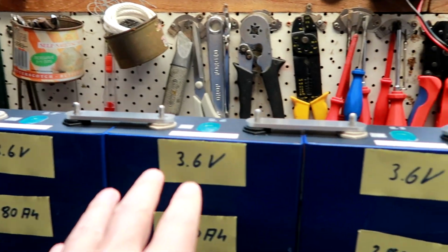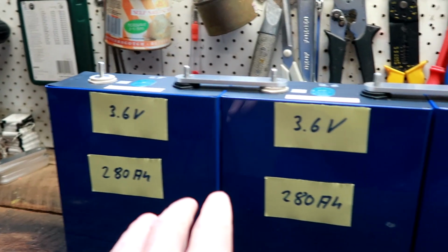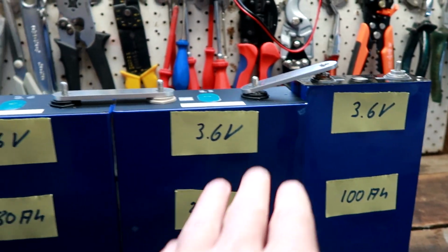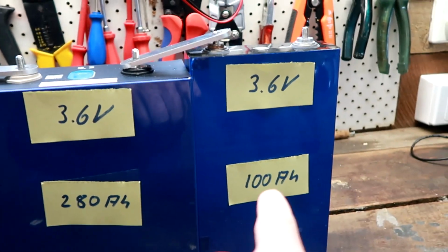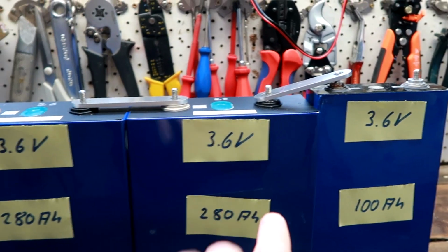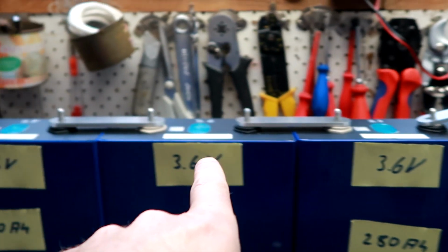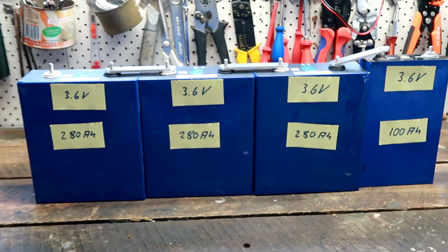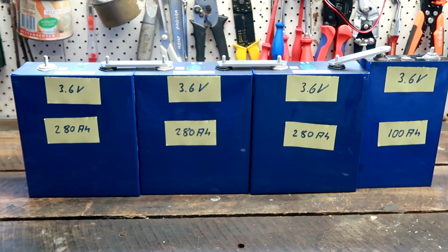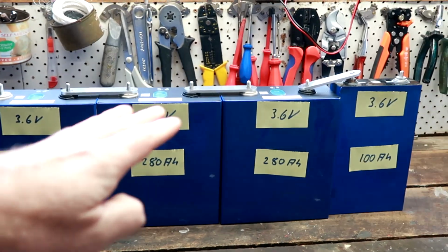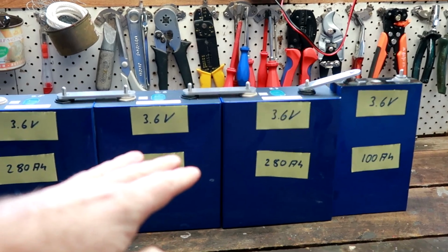3.6 volt, 3.6 volt, 3.6 volt, 3.6 volt. After balancing, you know, you did the balancing with your power supply. Everything is 3.6 volts and you've got them charged to the maximum state of charge at 3.6 volts per cell. They have, however, different capacities. But this is not what we are looking at. We are looking at the voltage. Voltage is 3.6, right? Okay, so, and now you're putting your battery on duty and start discharging your whole battery.